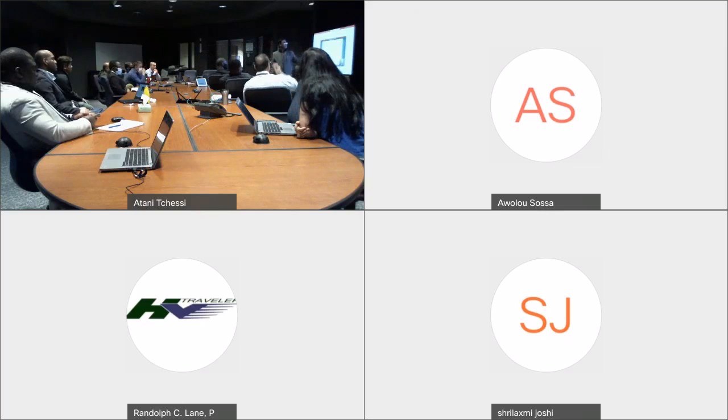So when you have this schematic drawing, it will be easy to interpret. I'll show you how it is connected, as Randolph told. See, this is the charger, and this is how the charger cable goes. The connector is here, and it is connecting here, and here. Everything you can trace from your schematic drawing, but from the physical setup you cannot. If you do not mark every individual cable with a marking, say 401, 402, you cannot correspond the cable with your physical setup. So marking is very important, but people don't always do the marking. Everything should be labeled properly.